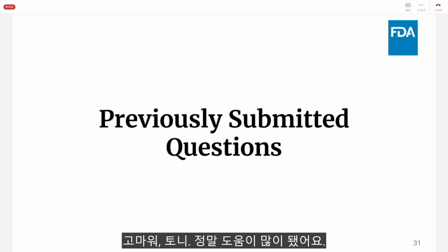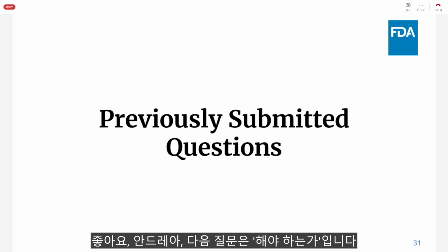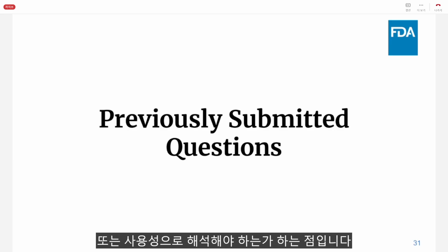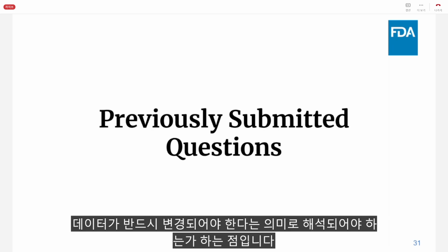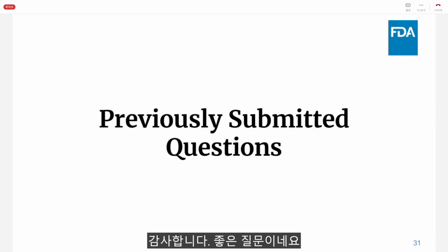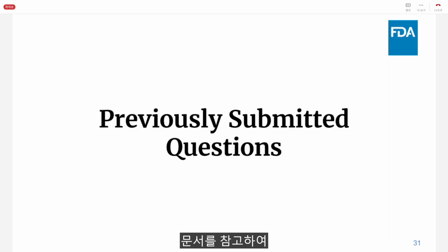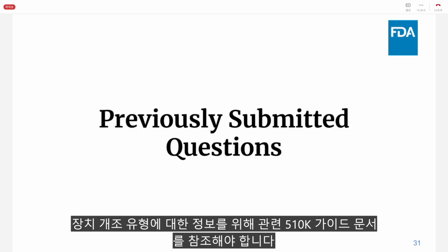All right, Andrea, the next question is, should the human factors content guidance be interpreted to mean that new human factors or usability data for changes to a currently marketed device must be submitted as a traditional 510K? Thanks. This is a good question. The human factors content guidance is not intended to identify what type of marketing submission is appropriate for a specific device or device modification. Instead, submitters should refer to the relevant 510K guidance documents for information about the types of device modifications considered appropriate for the different pre-market notification pathways.